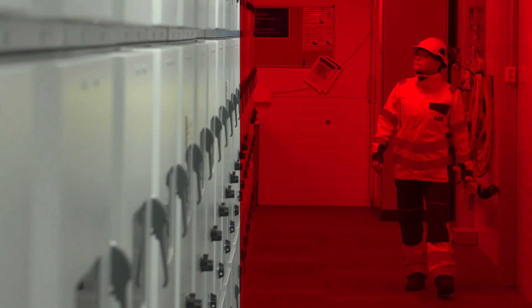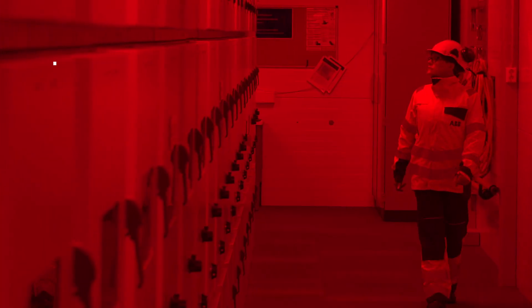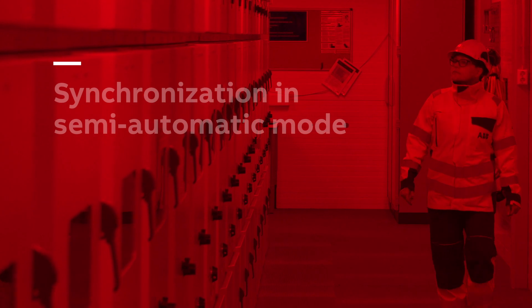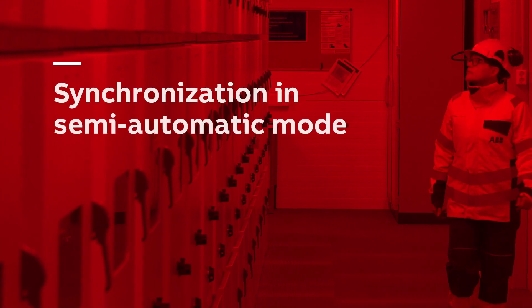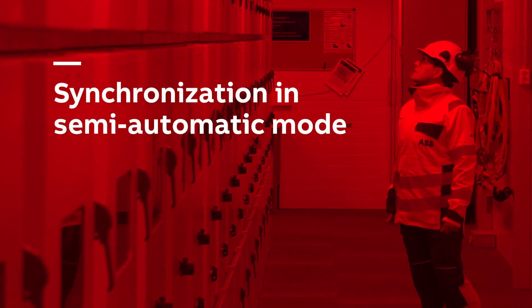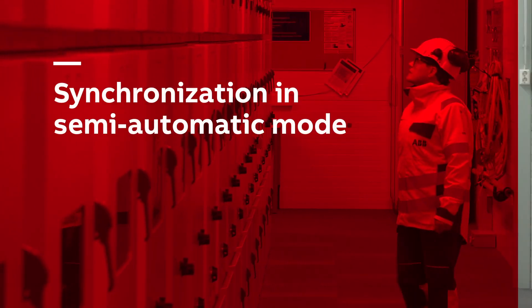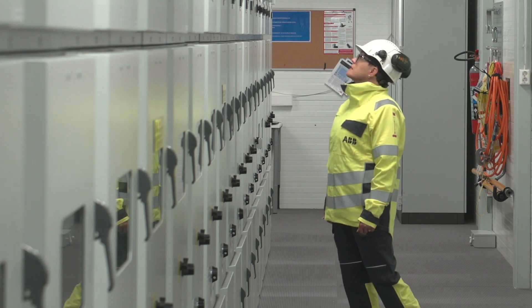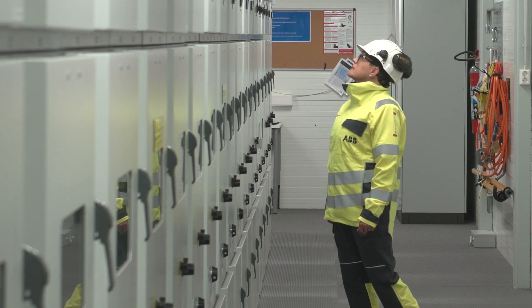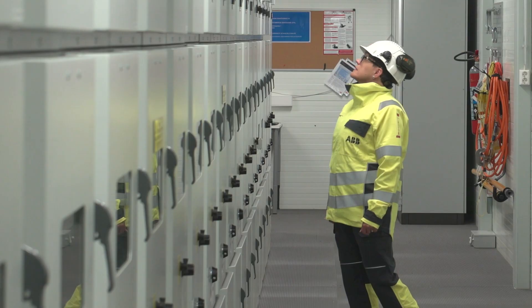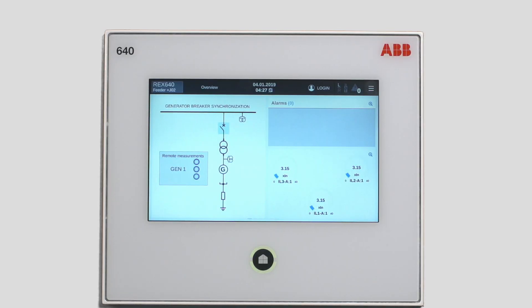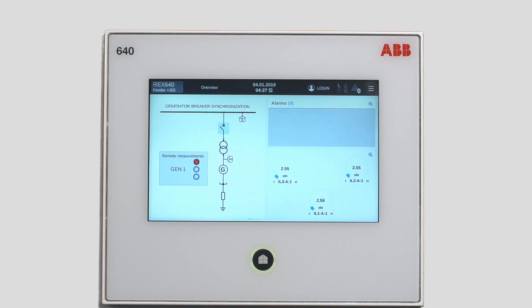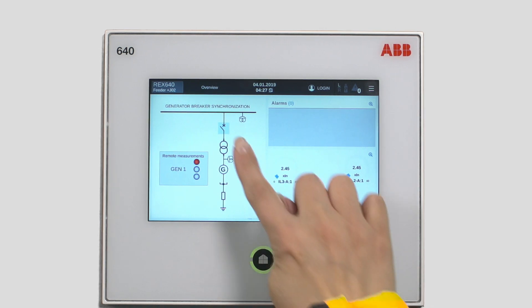After the first manual synchronization of the generator circuit breaker, the second synchronization could be done in semi-automatic mode. In this way, you are able to check the correct operation of the voltage and frequency matching functionality within the synchronizer and still remain in full control of the circuit breaker closing command.